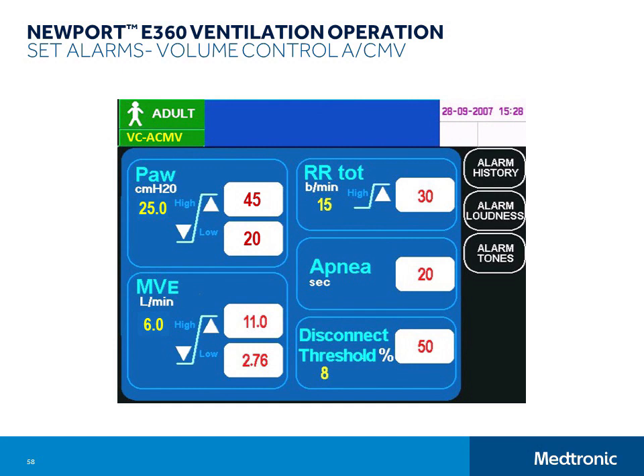Set the high and low minute volume alarms to bracket the patient's exhaled minute volume. Set the high and low airway pressure alarms to bracket the patient's peak pressure. Set the high respiratory rate alarm just above the maximum acceptable total respiratory rate. Set the apnea alarm at the maximum time allowable between breaths, and set the disconnect threshold alarm at the level of difference between the inspiratory and expiratory tidal volume that you wish the ventilator to use for declaring a circuit disconnect.